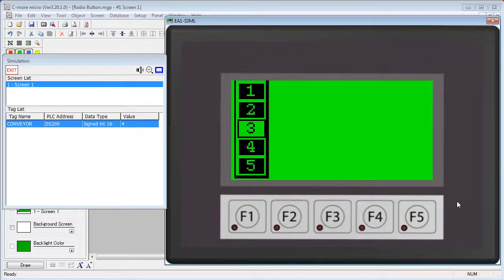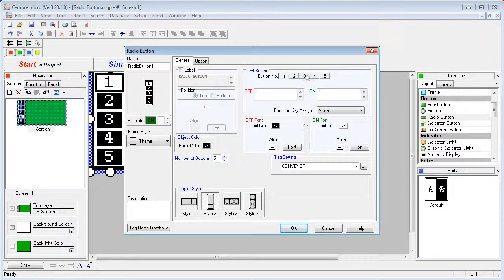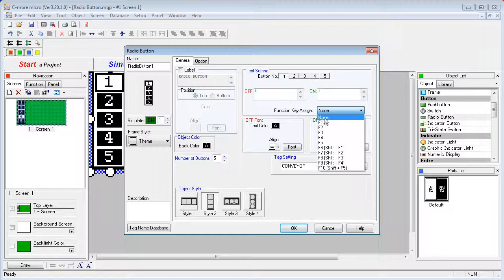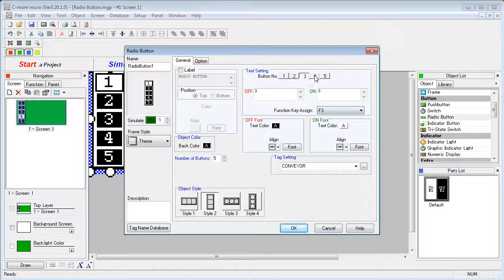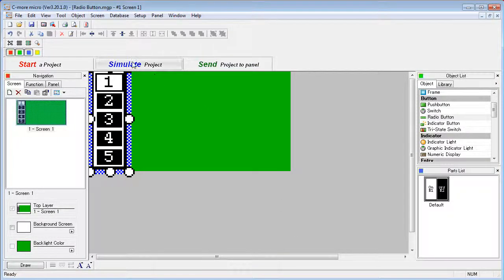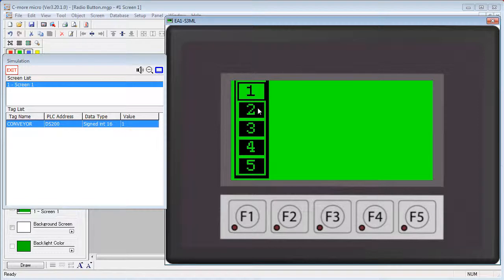What about the function keys on the front bezel of the C-more Micro? Can we use those to control the radio buttons? Sure, let's take a look. Go back to our project and double click on the object. Up here in the right-hand corner, you can select a function key for each button. So for button 1 we'll select function key 1, for button 2 function key 2, for button 3 function key 3. Notice that function keys 1 and 2 are no longer available — you can only have one function key per button. Let's finish this out: assign 4 to 4 and finally 5 to 5. Press OK, simulate, and save the project. Now in addition to our touch screen modifying both the buttons and the tag, our function keys do also.